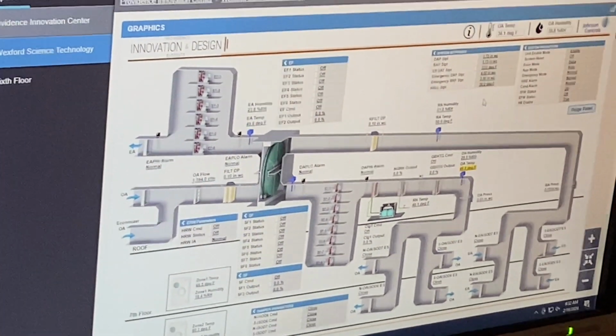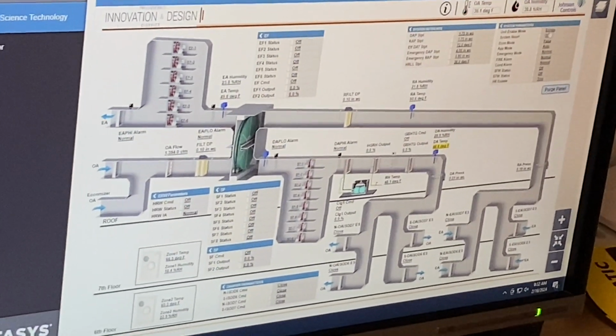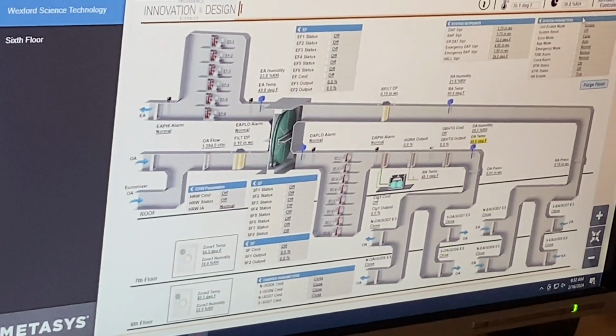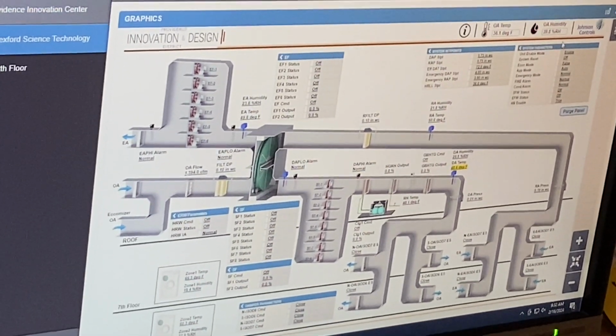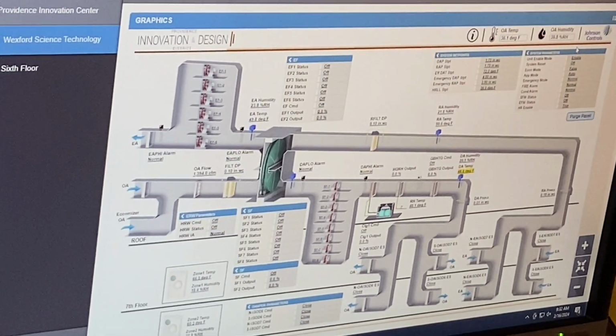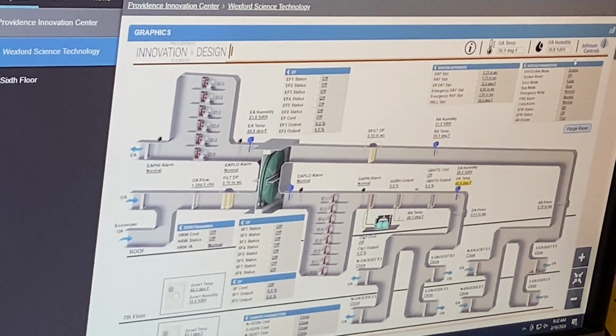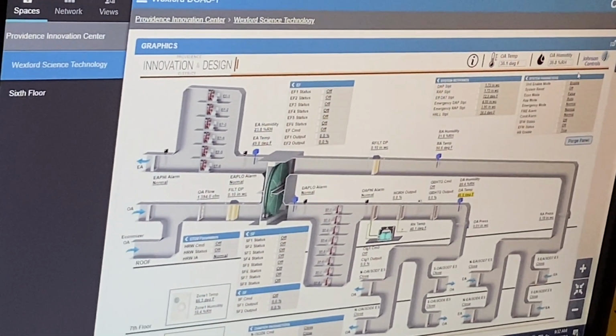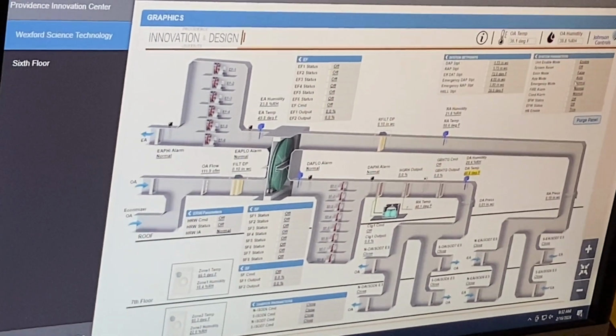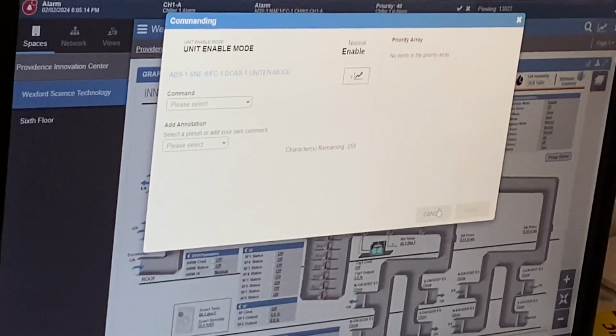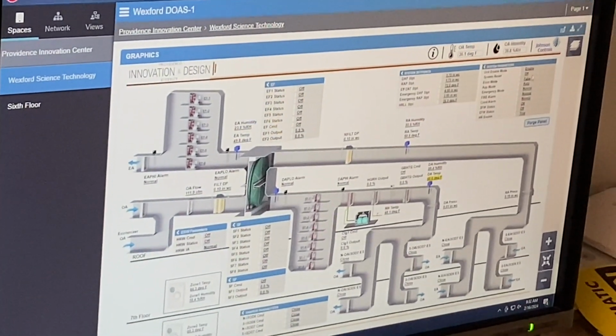Again, my biggest thing is if somebody's doing maintenance on the DOAS-1 unit, I always tell my customers: shut it down at the BMS system first. Because if you just go up there and start hitting disconnects, you're going to trip and cause alarms, and you're going to have to do a system reset. So you have a system reset on there on the screen — yes, it's the next one down, system reset right below it.